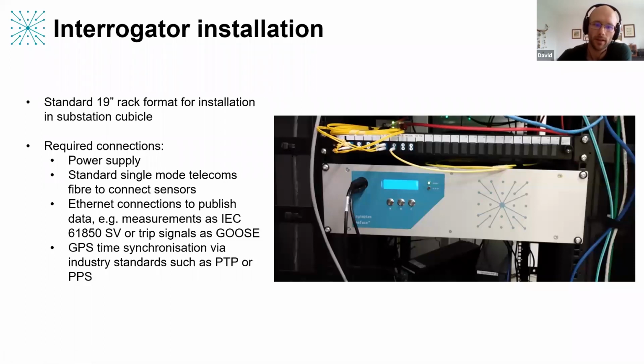These are published either as the measurements as IEC 61850 sample values, or we can also publish trip signals if we have a protection scheme running, and these are published as GOOSE signals. Further, we require GPS time synchronization of the system, and that is done via industry standards such as PTP or PPS.